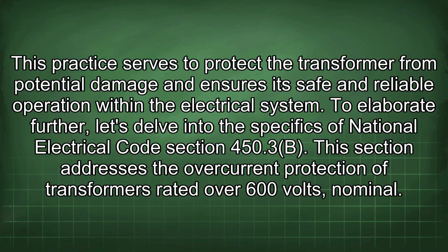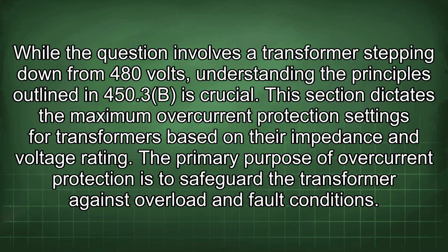the electrical system. To elaborate further, let's delve into the specifics of National Electrical Code Section 450.3b. This section addresses the overcurrent protection of transformers rated over 600 volts, nominal. While the question involves a transformer stepping down from 480 volts, understanding the principles outlined in 450.3b is crucial. This section dictates the maximum overcurrent protection settings for transformers based on their impedance and voltage rating.